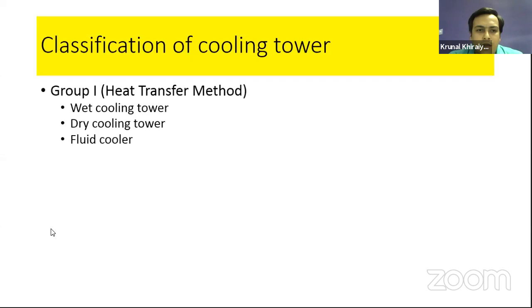So whenever we have chemical industries and these special applications, we are not using wet cooling towers. We are using dry cooling towers and fluid coolers. Wet cooling towers are used in DG sets, in HVAC systems, and in power plants. Then the second classification is based on the air draft. Air draft means the pressure difference between the tower and the atmospheric pressure of air.